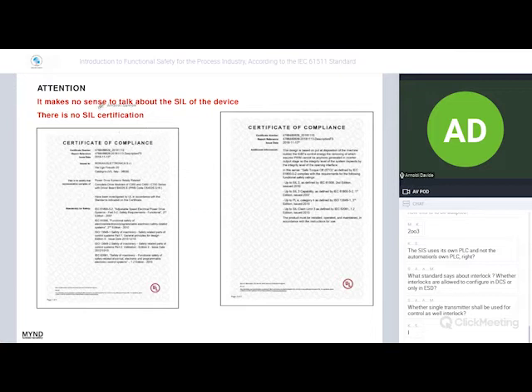Attention, it makes no sense to talk about the SIL level of a device. And the second thing is there is no SIS certification. The certification that we receive from the manufacturer is the compliance with 61508. So the certification is the 61508 compliance. It's not SIS certification. And normally in the certification there is a SIL level for the device. But it's not the SIL level of the device. It's the maximum SIL level of the function where we can install the device.